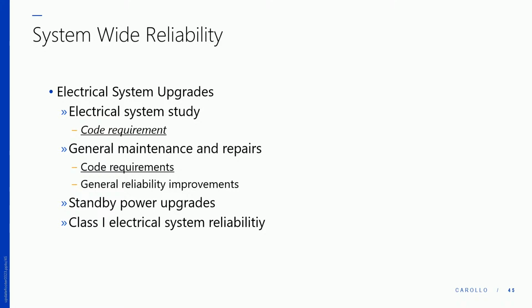So before I get into recommendations, I'll give you a brief overview: what do you currently have at the water plant? Currently you have a radial electrical system. What does that mean? That means that you have one electrical utility line coming into the facility. That utility line connects your utility transformers throughout, which distribute power to the electrical equipment that powers the electrical loads at the plant. If there were to be a fault, whether it be an arc flash fault or a short circuit fault, at any point in the system, there could be operational issues, and you could be out of commission.